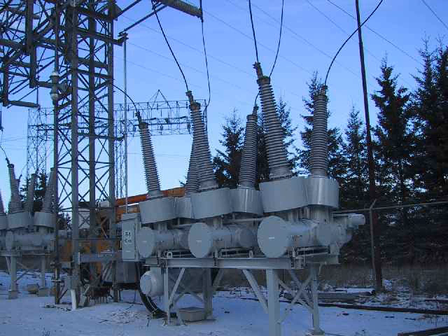High voltage 15 kV to 161 kV load switches were developed with a breaking capacity of 600 A. The first high voltage SF6 circuit breaker, built in 1956 by Westinghouse, could interrupt 5 kA under 115 kV, but it had six interrupting chambers in series per pole. In 1957, the puffer type technique was introduced for SF6 circuit breakers, wherein the relative movement of a piston and a cylinder linked to the moving part is used to generate the pressure rise necessary to blast the arc via a nozzle made of insulating material. In this technique, the pressure rise is obtained mainly by gas compression.